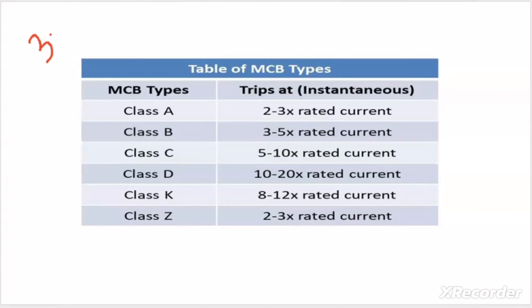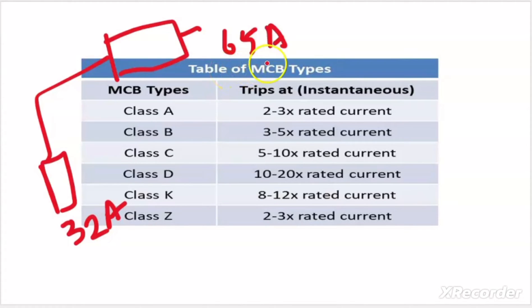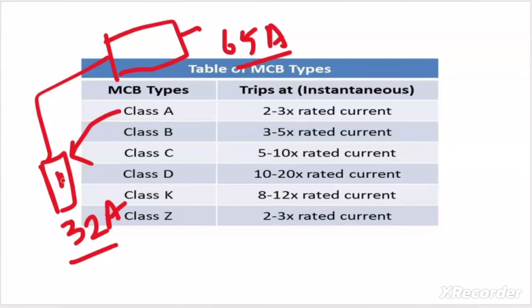For example, suppose I have a 32 ampere circuit breaker with a C curve rating, and it is feeding a motor that draws 65 ampere at startup. That inrush current is greater than the circuit breaker rating, which would normally cause it to trip. However, we know this 65 ampere inrush current at starting is temporary and will vanish in 3 to 4 seconds. The curve rating allows the circuit breaker to hold this 65 ampere for that interval without tripping, which is our desired requirement.